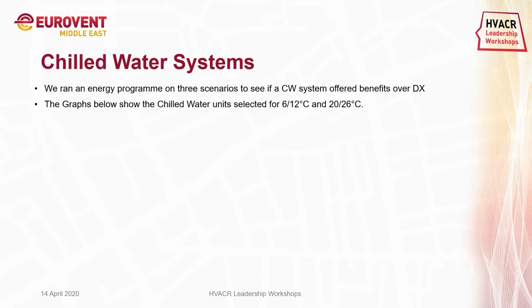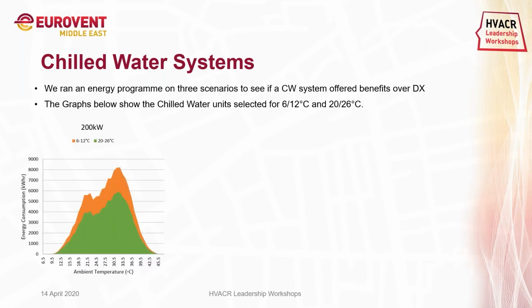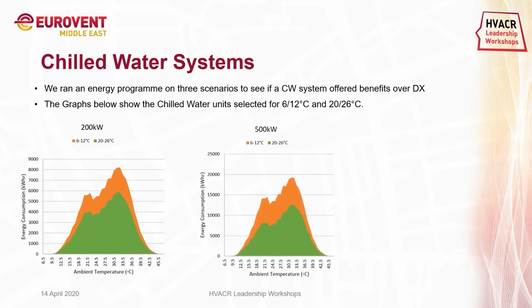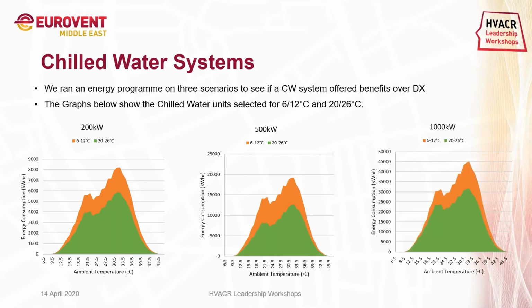So we ran an energy program in 3 different scenarios to see if a chilled water system offered any benefits over the DX system, which we discussed before. For this, we have taken 2 different chilled water temperatures, one is 6/12 and one 20/26. For a 200 kilowatt facility, we have plotted the energy consumption with the 2 different chilled water temperatures. The orange color you can see is 6/12 degrees Celsius, and 20/26 is the green color. So you can see a saving in energy consumption while we are using higher chilled water temperatures. For a 500 kilowatt facility, the energy consumption is much lower. For 1000 kilowatt, with the higher temperatures, the energy consumption is much lower.